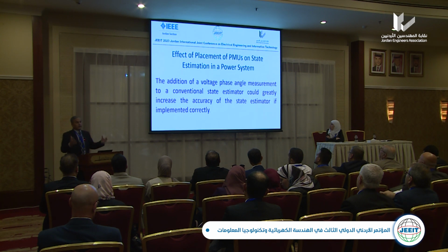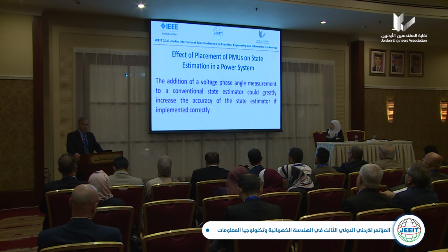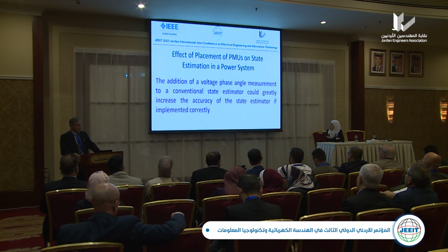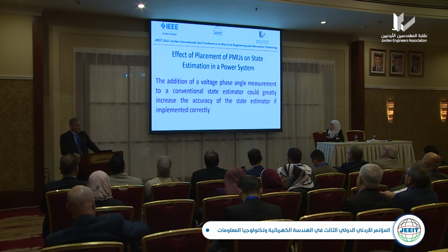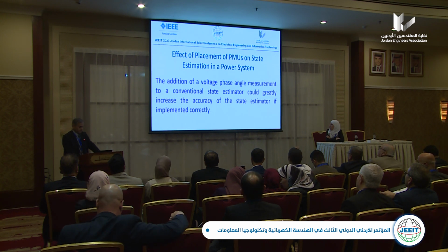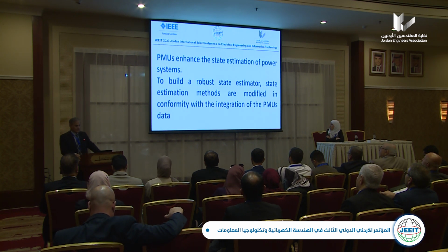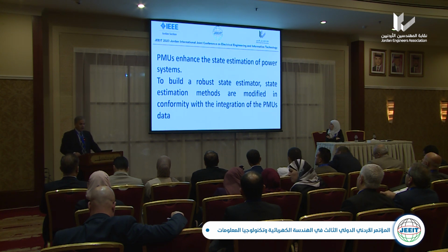Combining PMUs and the state estimator, the addition of a voltage phase angle measurement by the phasor measurement units to a conventional state estimator could greatly increase the accuracy of the state estimator if implemented correctly. So PMUs enhance the state estimation of power systems. To build a robust state estimator, state estimation methods are modified in conformity with the integration of PMU data.